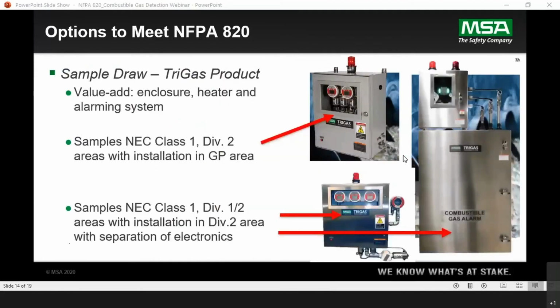So, sample draw, again, more information about that. The Tri-Gas product, which was released a number of years ago, we basically add value to. So we add an enclosure, a heater for freeze protection, and an alarming system. The alarming system would be lights, a strobe, and an internal buzzer. So for example, if it's a Class 1, Division 2 area, the sample is pulled from there to this box. This is a general purpose box, so this needs to be in a general purpose area. It's designed for that use.